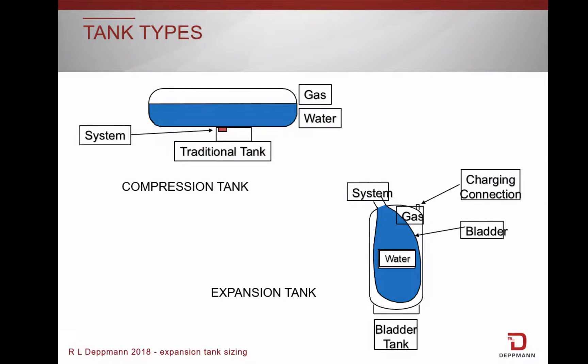In this slide, you will see the two different types of expansion tanks. Things in common: all are connected to the system, and all contain system fluid and a compressible gas. A standard or compression tank allows gas and fluid to be in contact, while diaphragm and bladder tanks have impermeable rubber membranes. The diaphragm and bladder tanks can be pre-charged with air or nitrogen.